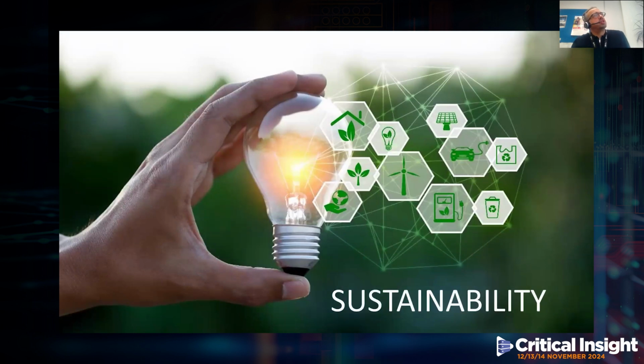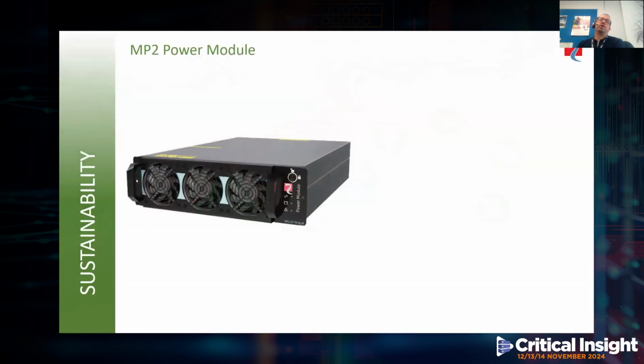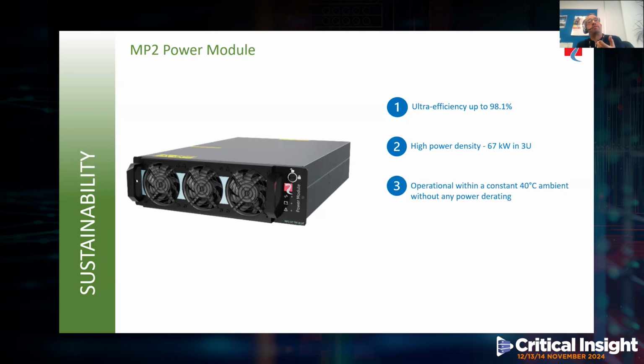So the question we need to ask is, what actually makes the Multi-Power 2 sustainable? Well, it all starts with the power module, which has been specifically designed with sustainability in mind. Now, the module itself can achieve an efficiency of up to 98.1%, so the heat loss is minimized. It has a high power conversion density at 67 kilowatts in just 3U, so the modules are compact. It can operate permanently within a 40-degree ambient without any power derating. It has a very high DC to AC conversion efficiency, so no battery energy is being wasted. And finally, it has an efficiency control mode, which can dynamically adjust the number of active modules in order to maintain a constant high level of efficiency throughout all modes of operation.